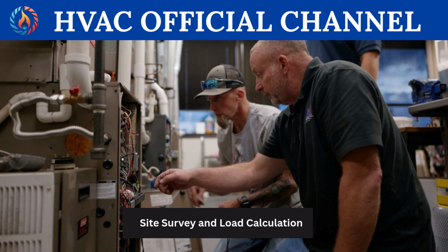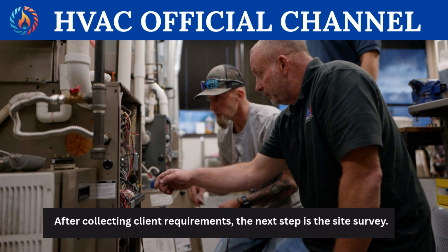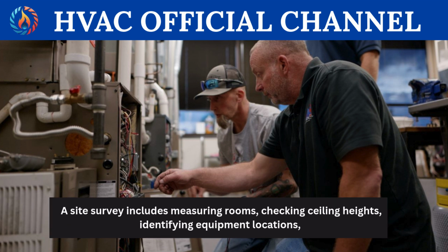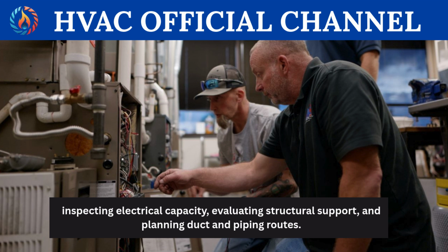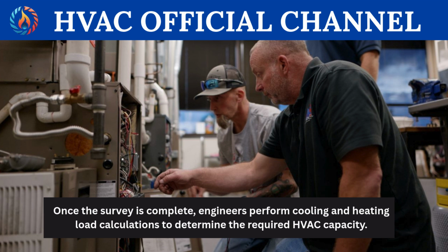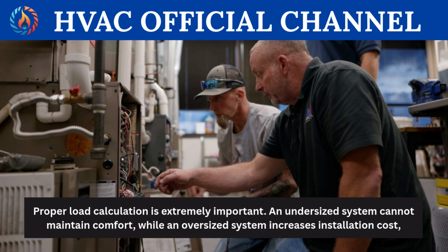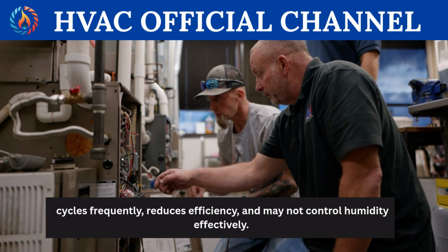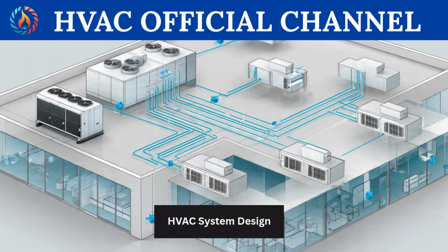Site survey and load calculation. After collecting client requirements, the next step is the site survey. A site survey includes measuring rooms, checking ceiling heights, identifying equipment locations, inspecting electrical capacity, evaluating structural support, and planning duct and piping routes. Once the survey is complete, engineers perform cooling and heating load calculations to determine the required HVAC capacity. Proper load calculation is extremely important. An undersized system cannot maintain comfort, while an oversized system increases installation cost, cycles frequently, reduces efficiency, and may not control humidity effectively.